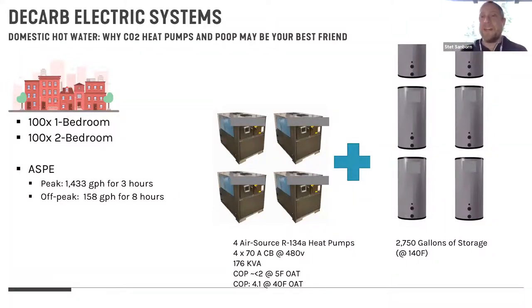Because that COP, when we see outside air temperatures fall into the teens, that COP is below 2. For us in our zone, in our utility structures, I need to see a COP of 3 on average for the year to be cost competitive with natural gas. So if I'm pushing too many hours of the year of the system into those nighttime hours, you're starting to run into a high cost component.